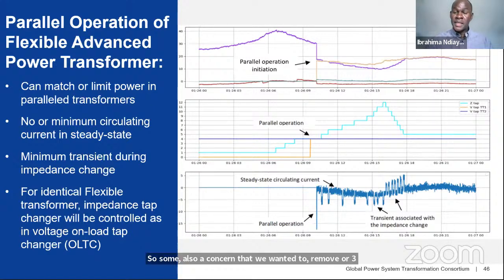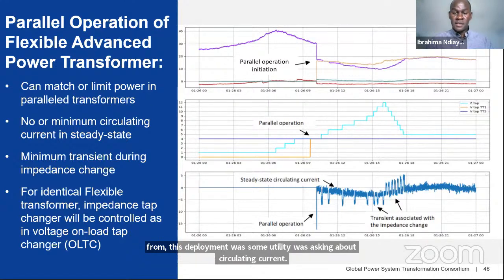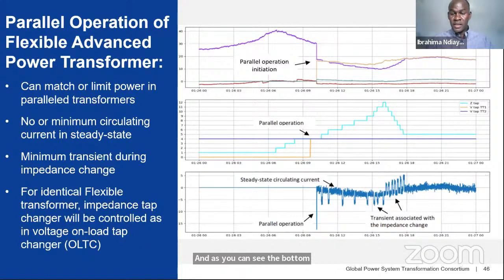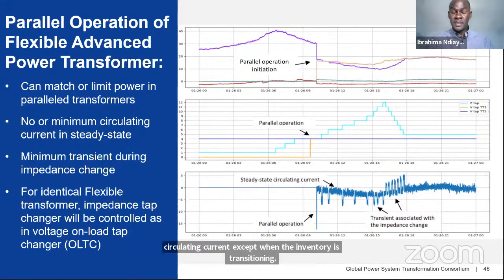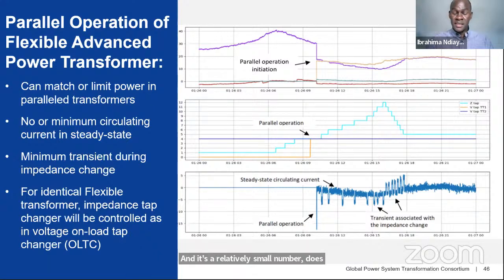Some utilities were also asking about circulating current, a concern we wanted to address from this deployment. As you can see, the bottom curve here in dark blue shows that there is pretty much no circulating current except when the impedance is transitioning, and it's a relatively small number. That's actually the only time that you can really sense that there is an active change of the leakage impedance. Other than that, there was no adverse impact on the grid side.